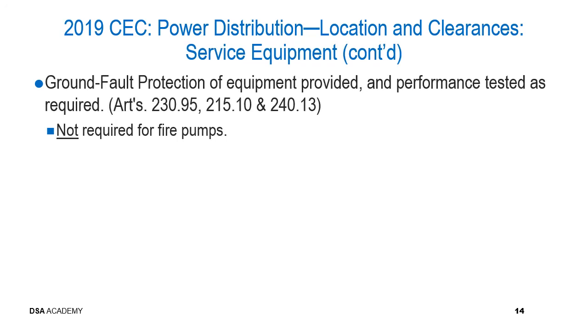Another thing that project inspectors are going to have to review for compliance is to make sure that any ground fault protection that is required for equipment is provided and is also performance tested as required. These requirements are detailed in Articles 230.95, 215.10, and 240.13. But remember, ground fault protection of fire pumps is not required. And that's pretty obvious. Since fire pumps are an emergency piece of equipment, they are not permitted to be on a ground fault protected circuit, or a circuit that is protected by a ground fault protector. They're treated completely differently since they are part of the emergency fire suppression system.